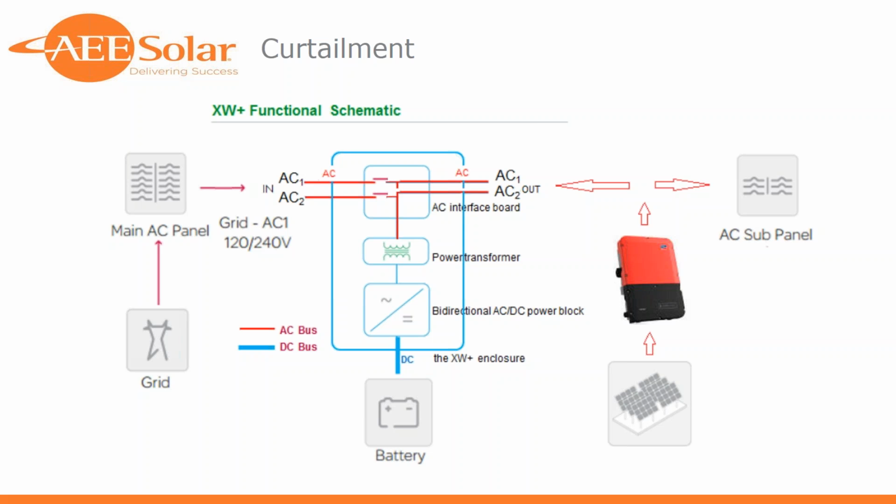So speaking here about curtailment, why is this important? In sizing an AC coupled system, we talked a lot about uncontrolled charge currents. Rather than belabor this point, I just want to speak to an experience I had working with one of the Solar Decathlon teams about 6 years ago. University of Tennessee had built this beautiful Solar Decathlon home. It had cylindrical tubes on the roof because they were really going for an aesthetic look. Basically it had 10 kilowatts of array, on two 3.8 kilowatt PV inverters. They did well at the competition, didn't win, but did really well.